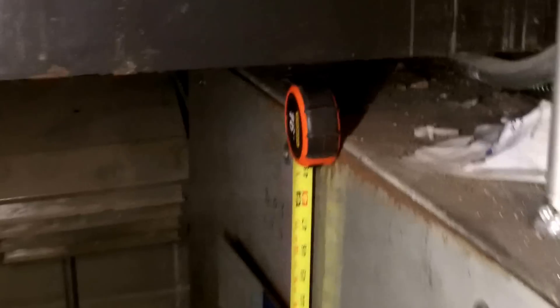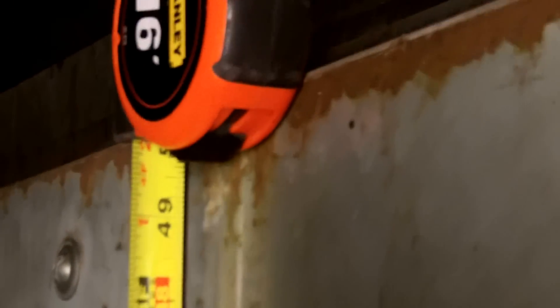But if we move in to my tape measure, we'll see that the headroom on this particular panel board is only 4 feet — a little more than 4 feet — until we hit this beam in the ceiling.